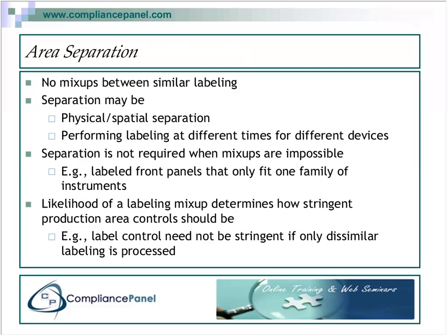Your separation has to be physical, spatial, if you will. The way you want to do this is to perform labeling at different times for different devices. This just increases the likelihood of no mix-up. Separation isn't required when mix-ups aren't possible. For example, if you stock labeled front panels that fit only one family of instruments, there's not going to be a problem, because they can't fit anywhere else. So when it comes to area separation, it's not critical that you practice that.